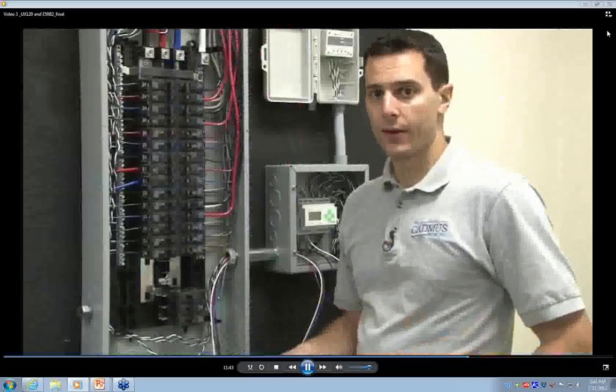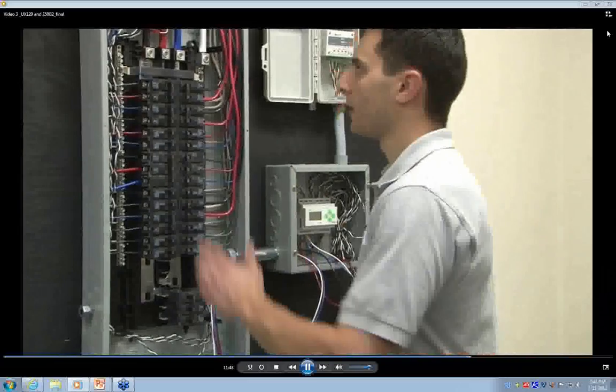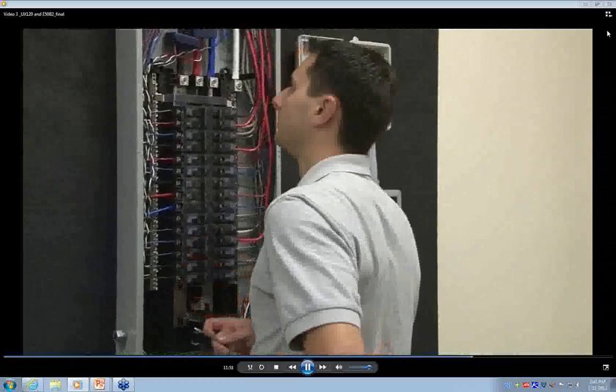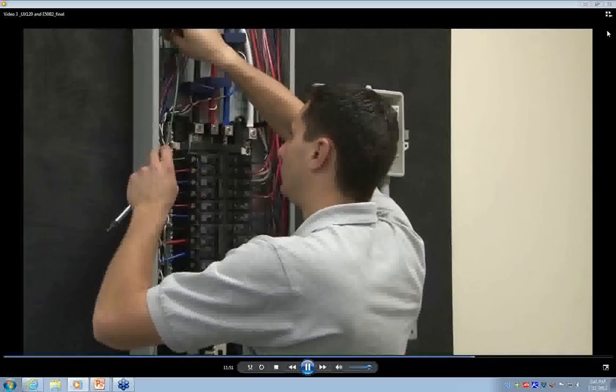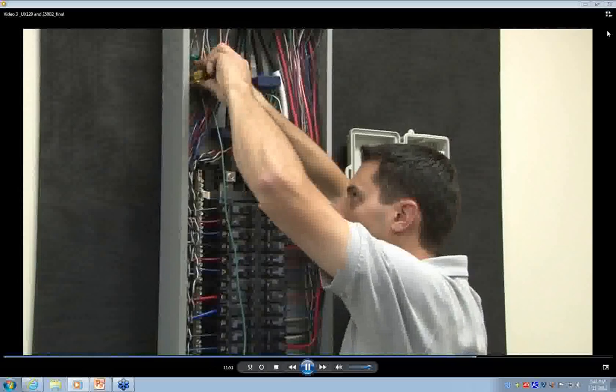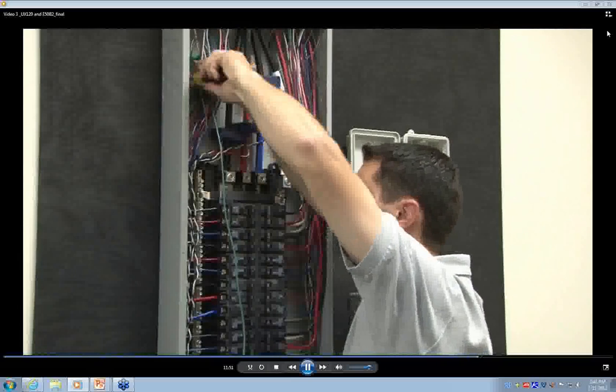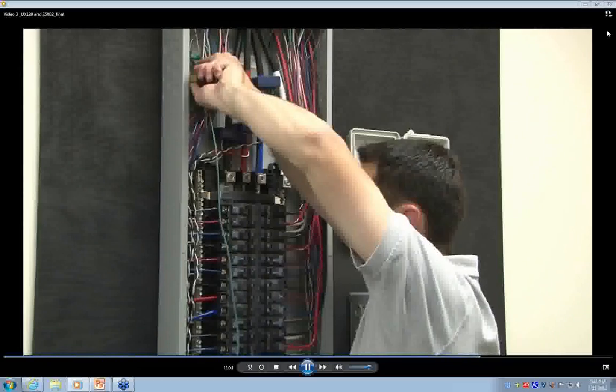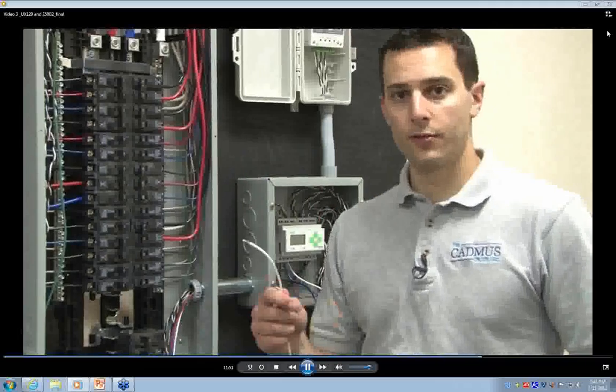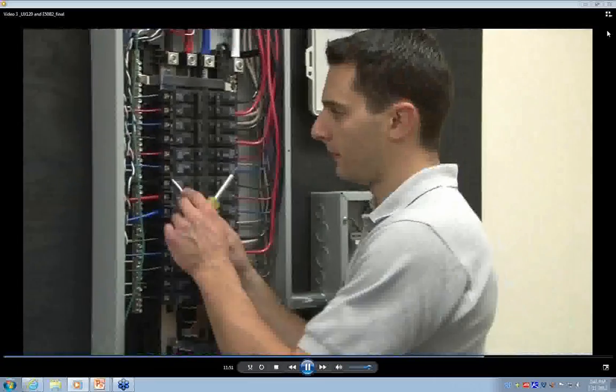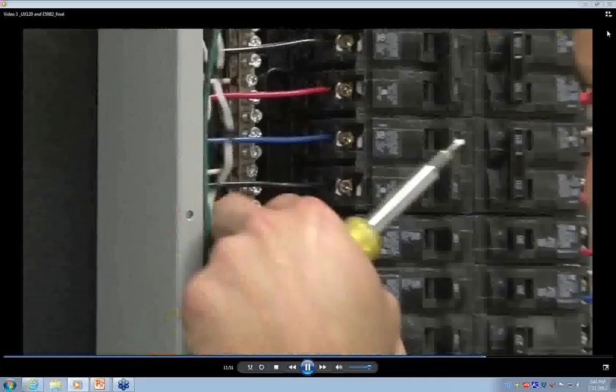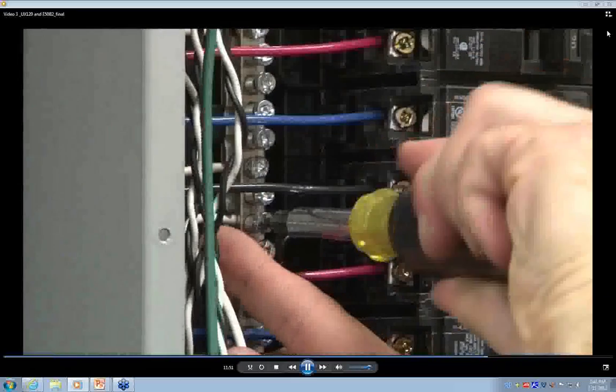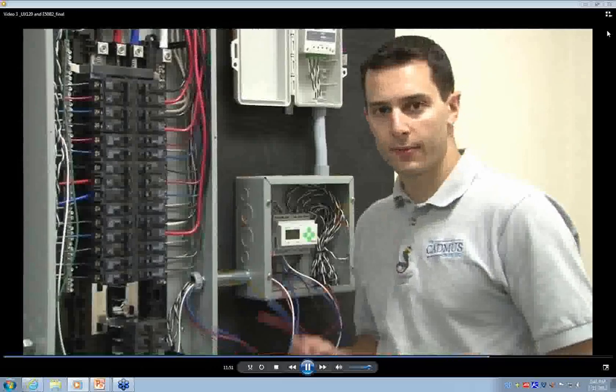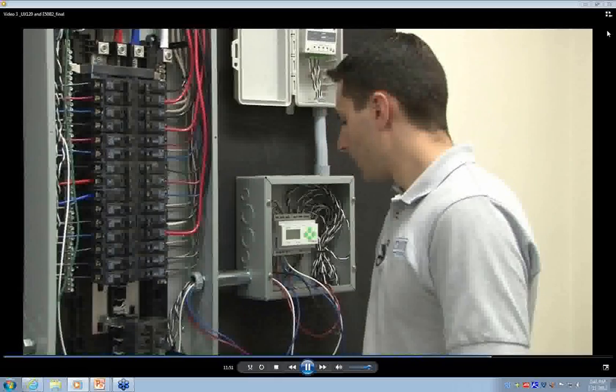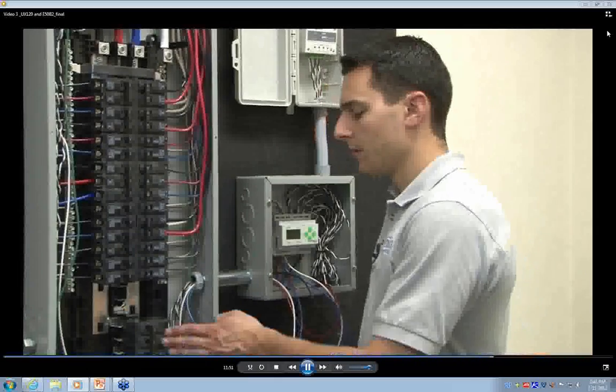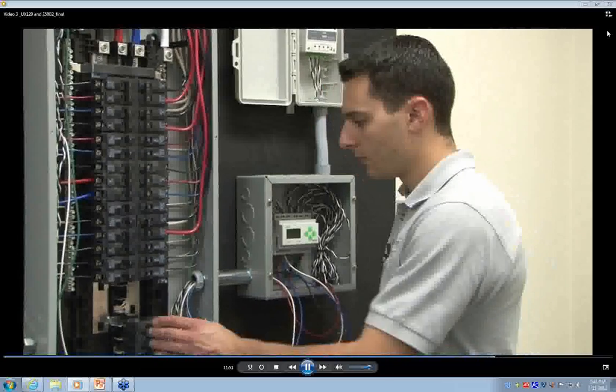We will now connect the green ground wire to anywhere on the ground bus bar, which is right up here. We'll now connect our white neutral conductor to the neutral bus bar. And now we'll connect our 3 voltage leads to a circuit breaker. For the safest installation, it's recommended that we use a 15 amp circuit breaker and we connect it right into the bus bar.